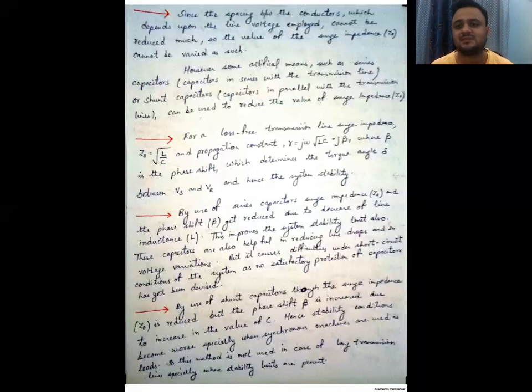So we look towards surge impedance to see how it can help increase our voltage level. By the use of capacitors, we can easily reduce the value of surge impedance and reach the stability limit, as well as increase the maximum power that can be transmitted through a transmission line.